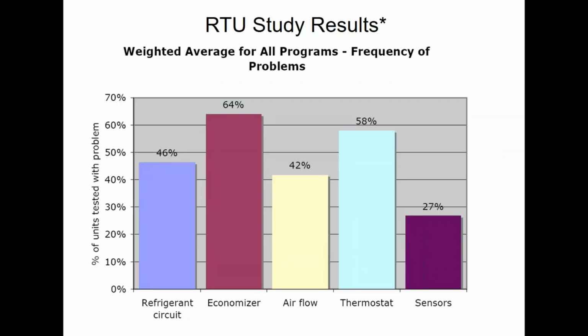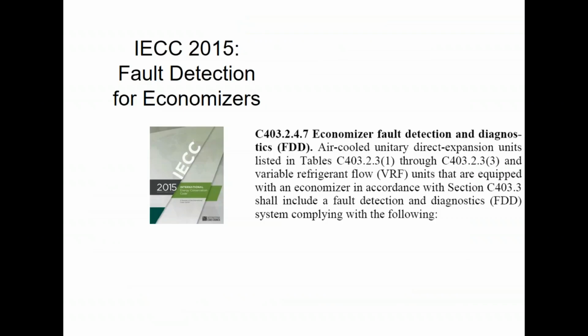You guys have seen this chart before, and you probably have heard me complain that a lot of economizers are not set up correctly, or they're screwed shut, or they're propped open, or the actuator's broke, or the linkages are broke, or whatever the case may be. There's numerous studies, including this one here, that points to, in this case, 64% of economizers not functioning correctly out in the field. So because of that, the energy code, both IECC as well as Title 24, which kind of feeds into a lot of these codes, requires something called FDD, Fault Detection and Diagnostics.